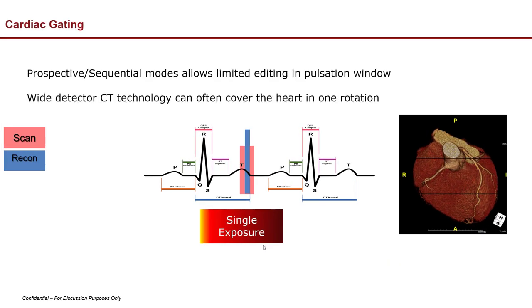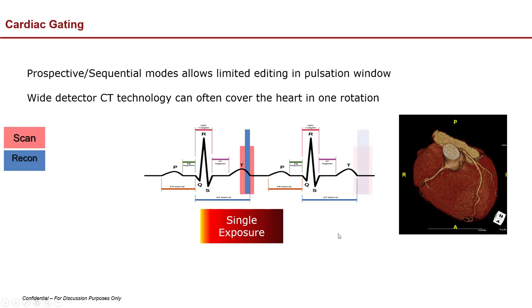There's limited editing here because whatever image you take, you're stuck with it. If the heart is a different size and shape due to a different heartbeat — whether faster or shorter — you're kind of stuck to that 4-centimeter gap or whatever the detector width is. That goes away when you have a wide detector system, because there are no gaps and you can image the heart in one rotation.